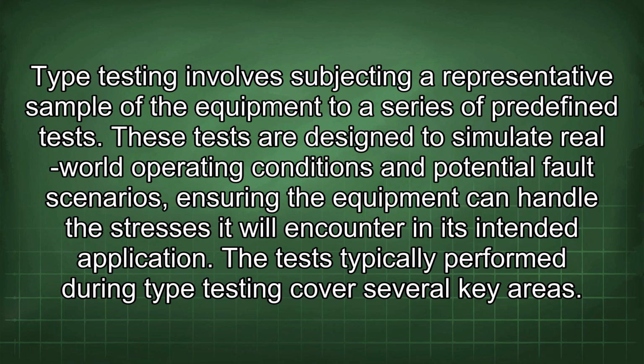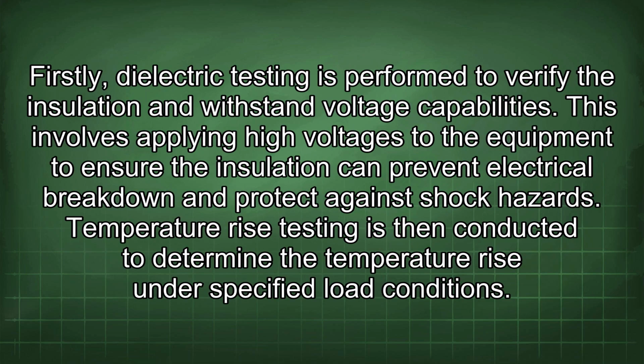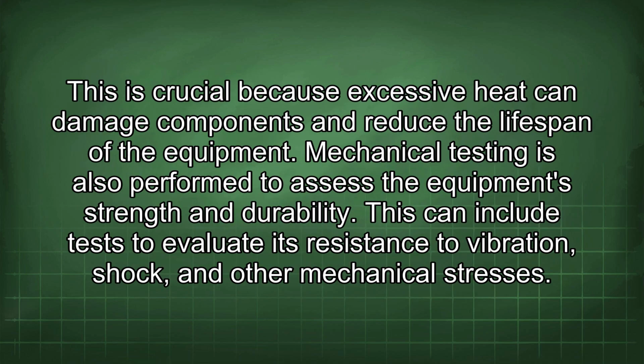The tests typically performed during type testing cover several key areas. Firstly, dielectric testing is performed to verify the insulation and withstand voltage capabilities. This involves applying high voltages to the equipment to ensure the insulation can prevent electrical breakdown and protect against shock hazards. Temperature rise testing is then conducted to determine the temperature rise under specified load conditions. This is crucial because excessive heat can damage components and reduce the lifespan of the equipment. Mechanical testing is also performed to assess the equipment's strength and durability. This can include tests to evaluate its resistance to vibration, shock, and other mechanical stresses.